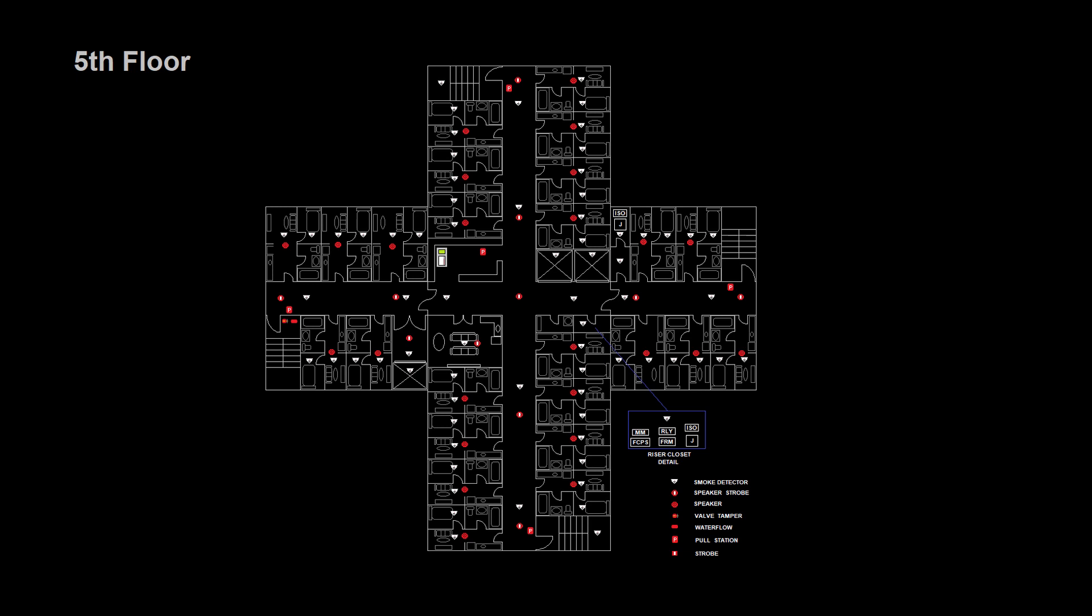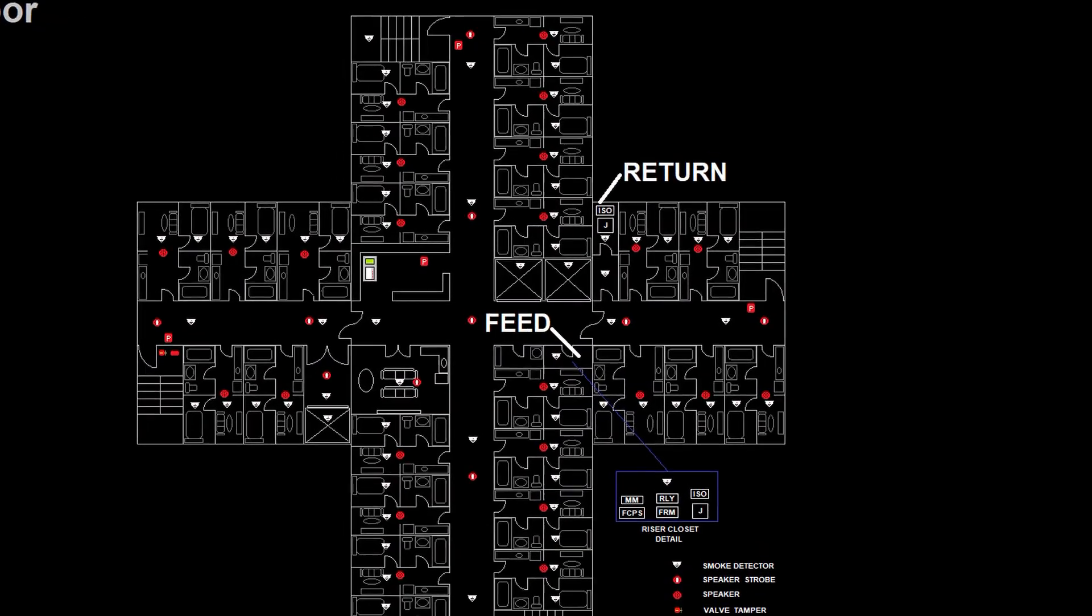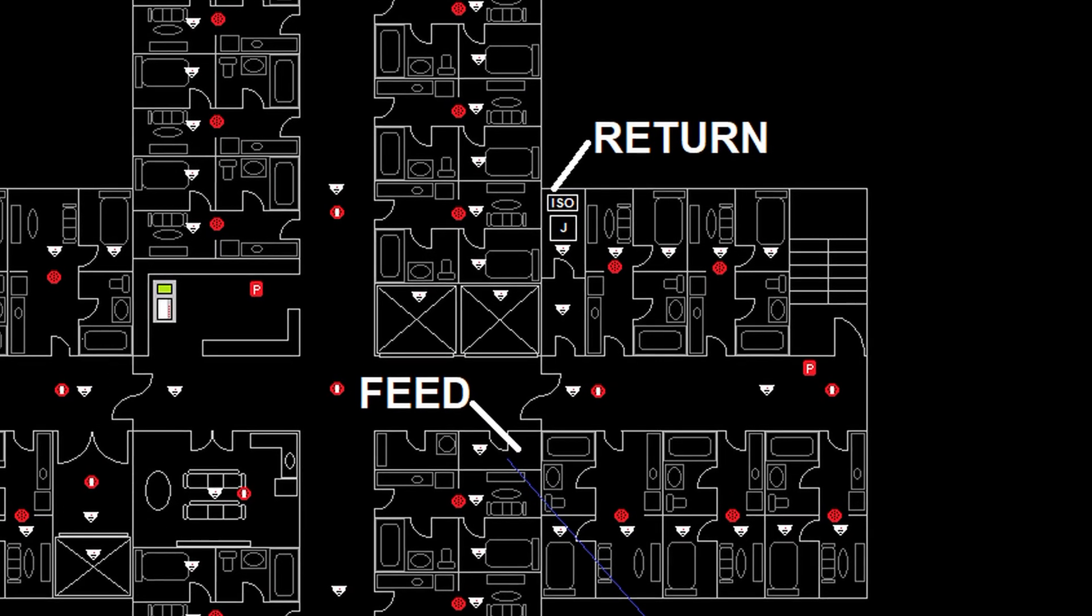To maintain proper Class A configuration, the feed and return pipes need to remain five feet apart, which in this case is no problem since our feed and return risers are in separate closets, as you can see here.